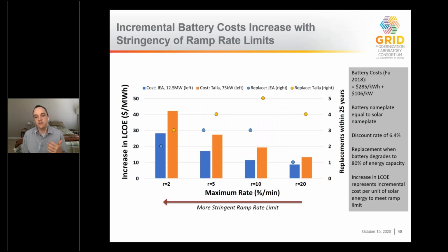So what we did was we then used this model to estimate the incremental increase in the cost of a PV system due to this additional battery equipment cost that you would add on to that PV plant to provide this ramp control. And we looked at this for different levels of stringency of that maximum ramp rate. So the more stringent you were, the more you wanted to really reduce those ramps and smooth out the output of that PV plant, the more you'd have to add additional battery equipment. In particular, you were increasing the duration of that battery to provide that ramp control. What that meant was that in order to meet that more stringent ramp rate limit, you would increase the initial cost of this.